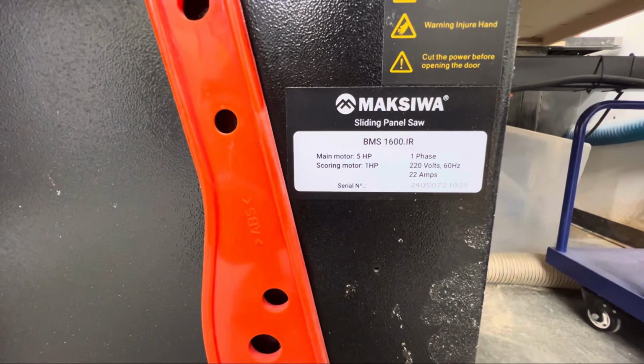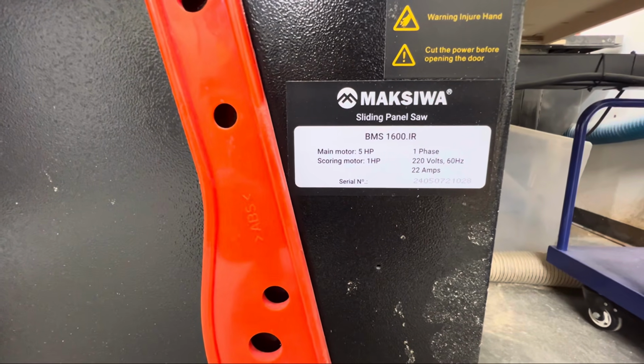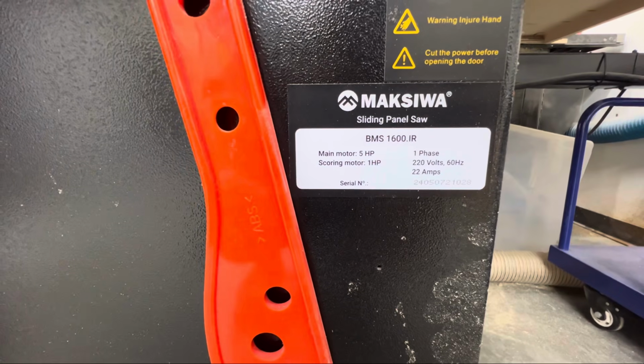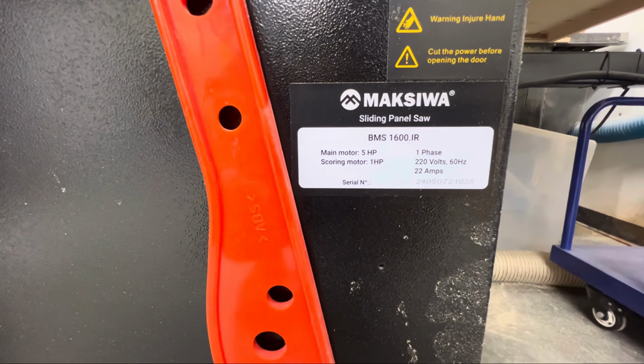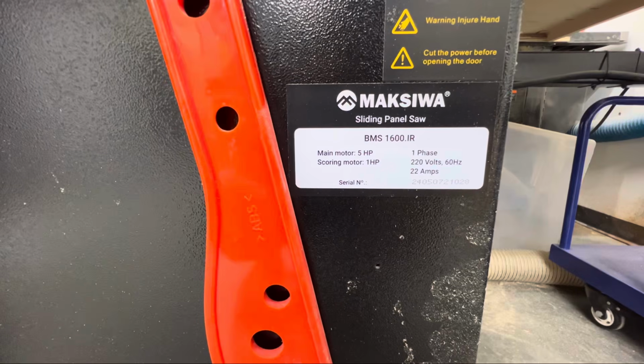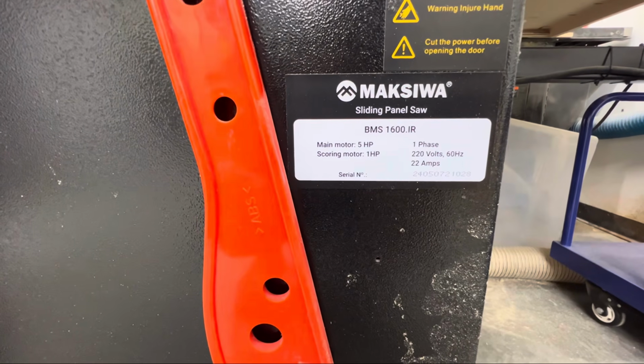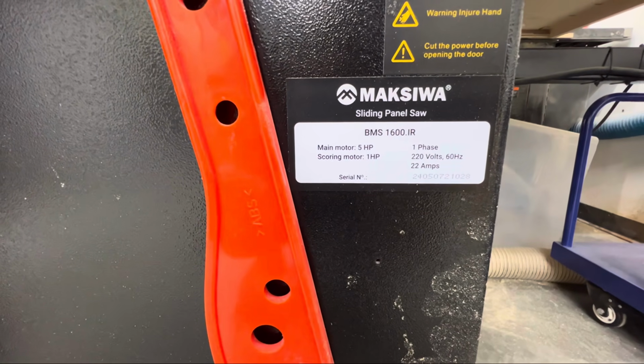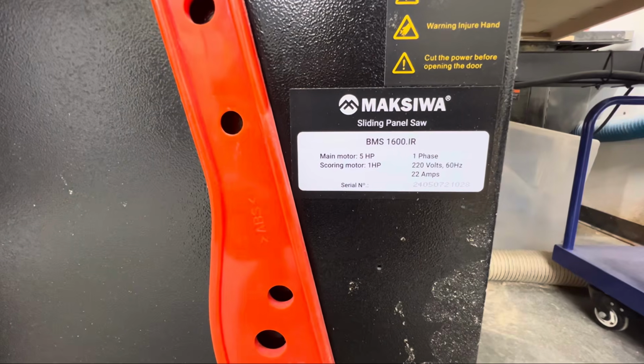Looking at the badge on the backside of the machine, we can see that we have a 5 horsepower main motor, a 1 horsepower scoring motor. This is a one-phase machine at 220 volts, and it runs on 22 amps, so you do need a larger breaker.